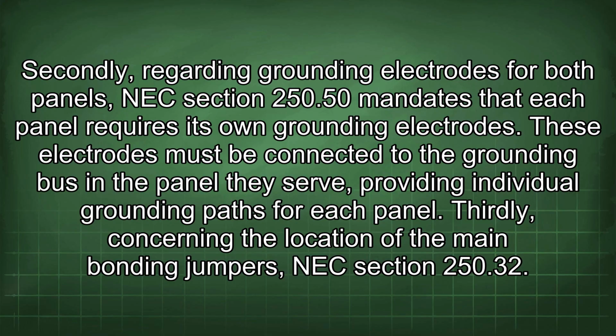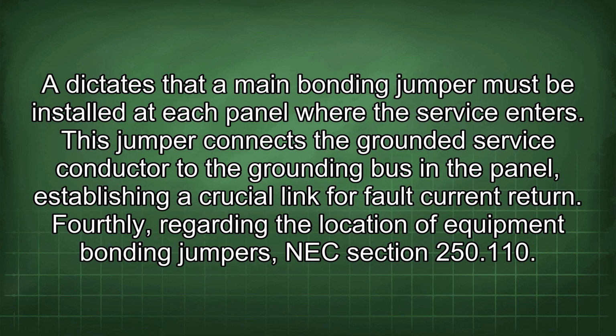Thirdly, concerning the location of the main bonding jumpers, NEC section 250.32 dictates that a main bonding jumper must be installed at each panel where the service enters. This jumper connects the grounded service conductor to the grounding bus in the panel, establishing a crucial link for fault current return.